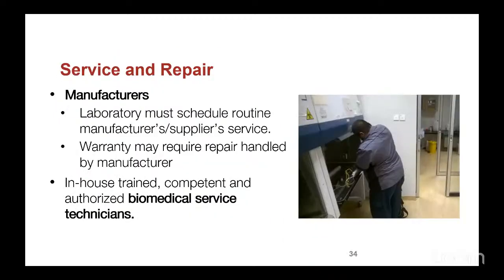Okay, service and repair. We look at the manufacturers. Laboratory must schedule routine manufacturer supplier services. Warranty may require repair handled by the manufacturer if that equipment is still under warranty. In-house trained, competent, and authorized biomedical service technicians can also be involved. So there are some organizations that have grown big to the extent that they have a biomedical service department that are in charge of such things.